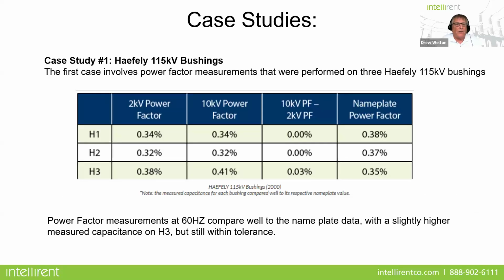Okay, so here's a case study. I've got a couple of case studies I'll share with you just to finish things up. What we saw here was your power factor measurements at 60 hertz compare well to the nameplate data. Okay, and you'll see here we did a tip-up test for all three bushings. They're well within range, fairly well within range of the nameplate data, with a slight difference in H3 and a slightly elevated difference from the nameplate rating.